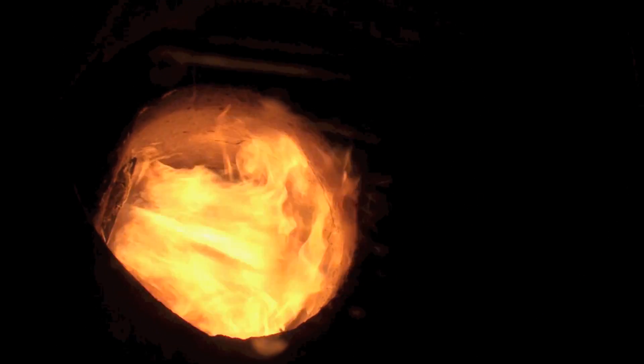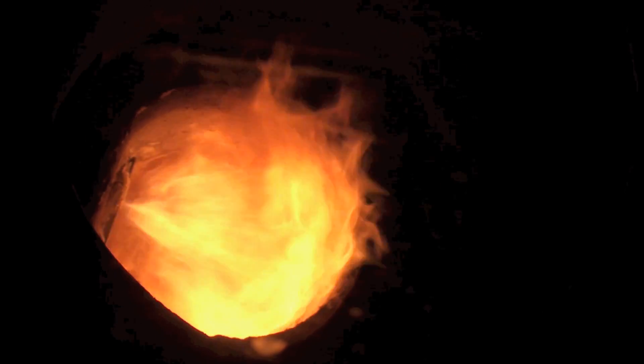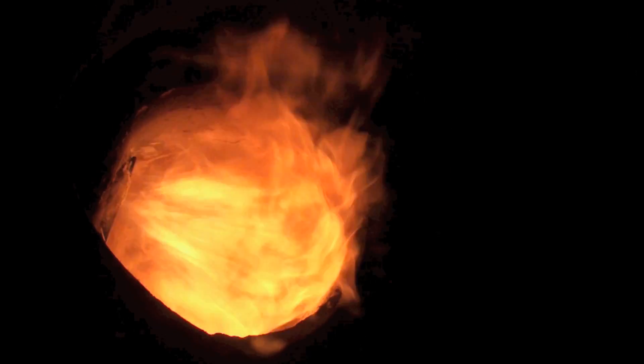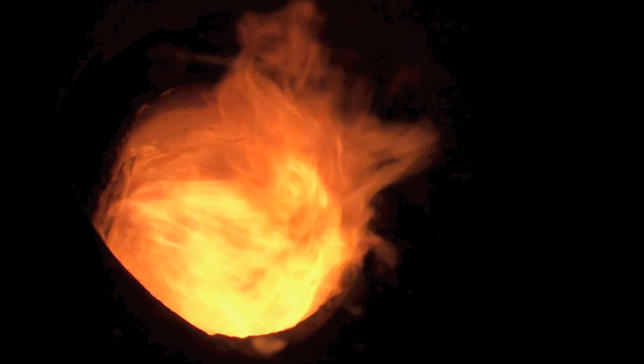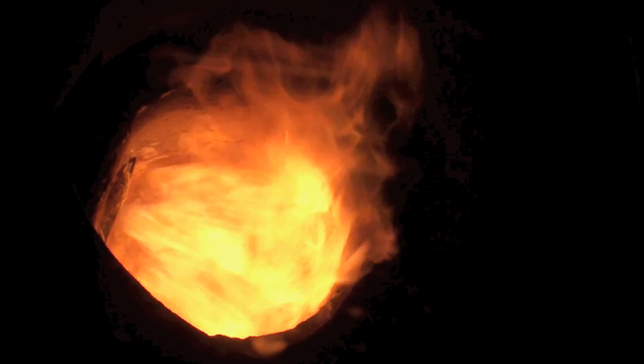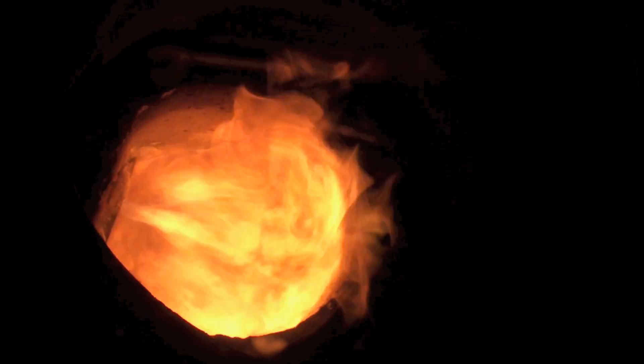Now I'm gonna start turning it back up again. You can see the flame is actually putting out more heat now. There's more flame to it. It's not a good flame because there's smoke in it. You really can't see the smoke but there is smoke in it and that's going to plug up the heat exchanger. So now we go back again.